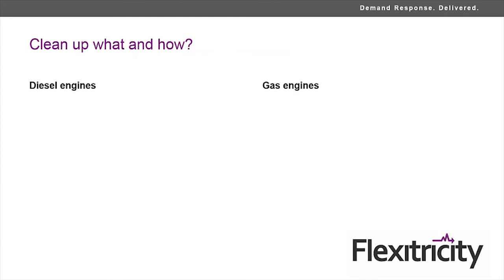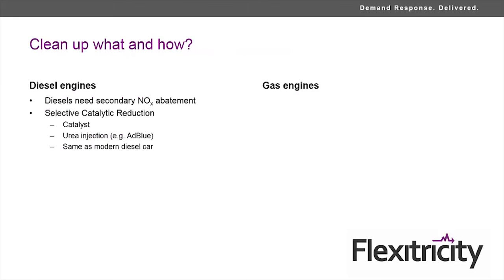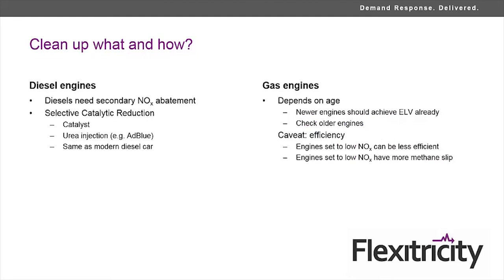So, cleaning up: if you have a diesel engine, there is no way that you're going to comply with these limits unless you have secondary NOx abatement. Selective catalytic reduction is the method - it's a catalyst and urea injection, basically the same as a modern diesel. Gas engines, generally speaking, tend to achieve these emissions limit values already. Older engines, it is absolutely worth checking.